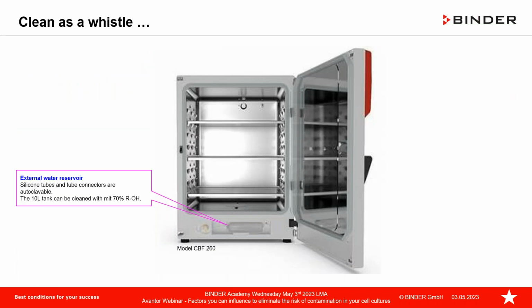And actually the hot air sterilization routine. What we also have as an alternative to the good old established water pan, as I said, is the possibility of external water reservoirs, either with bags, with refillable containers, or some manufacturers even offer pre-filled bottles, or one tank feeding these smaller reservoirs, depending upon type, model and manufacturer. So that's also something you would want to consider, because then you're removing that potential hazard, that possible risk of a water pan.